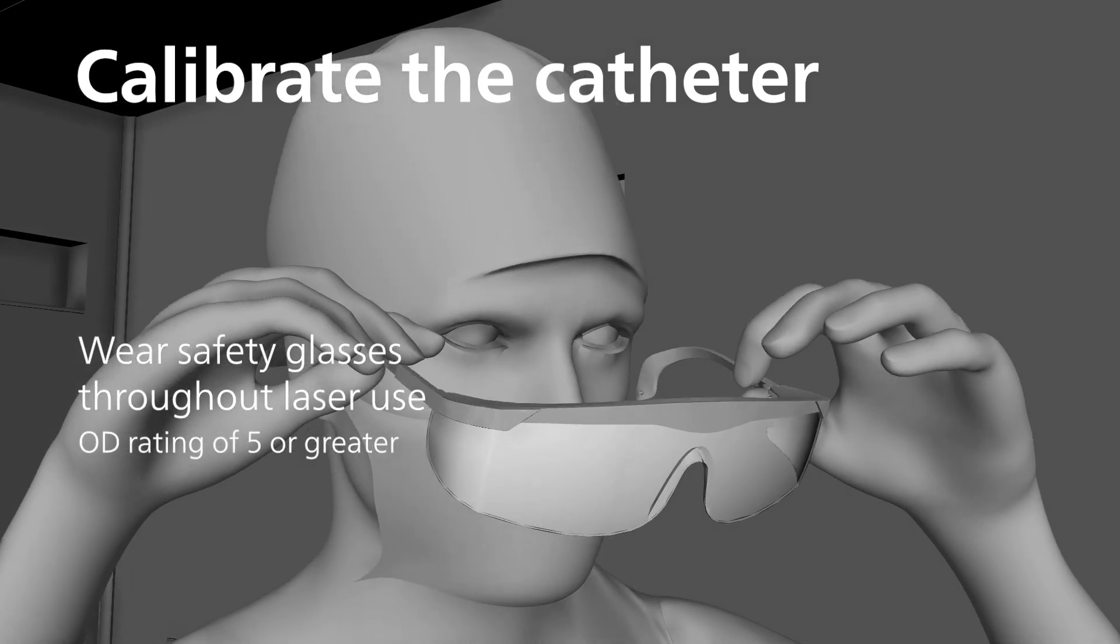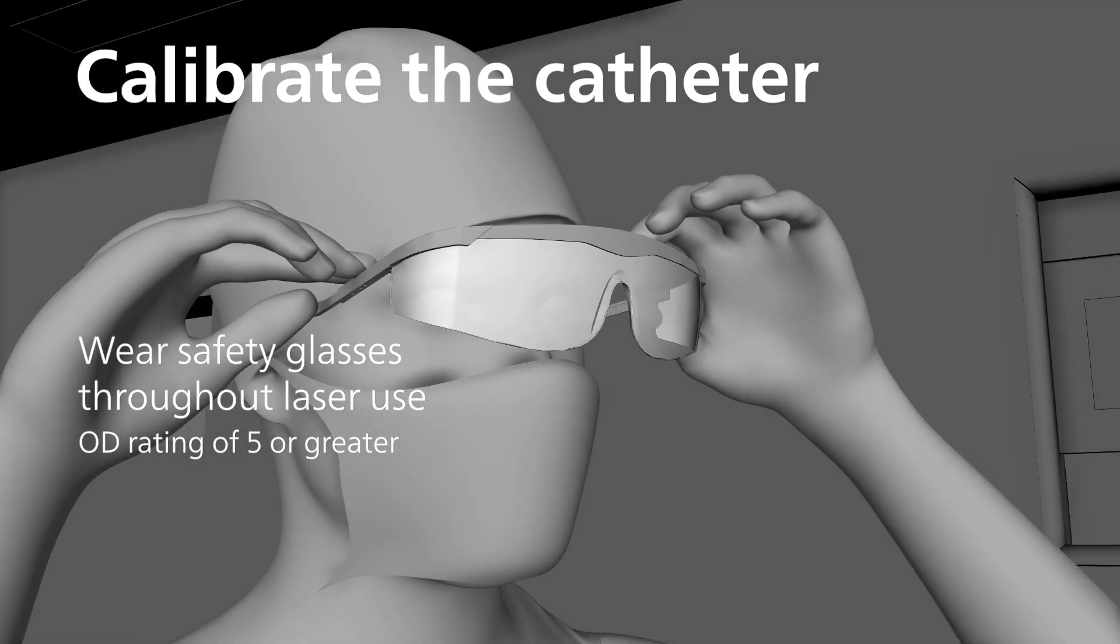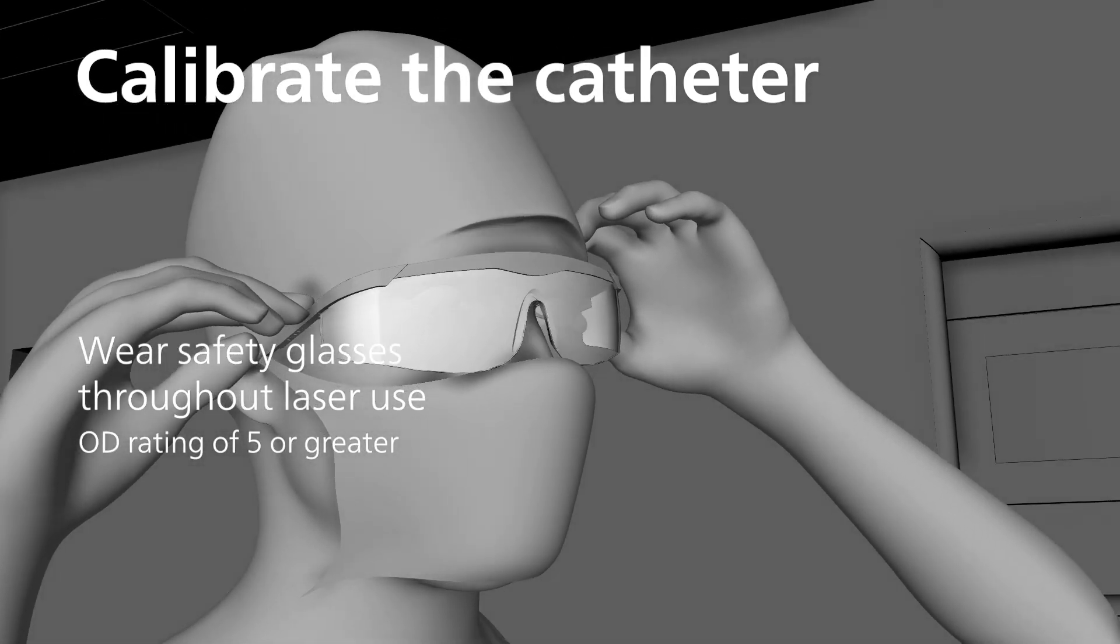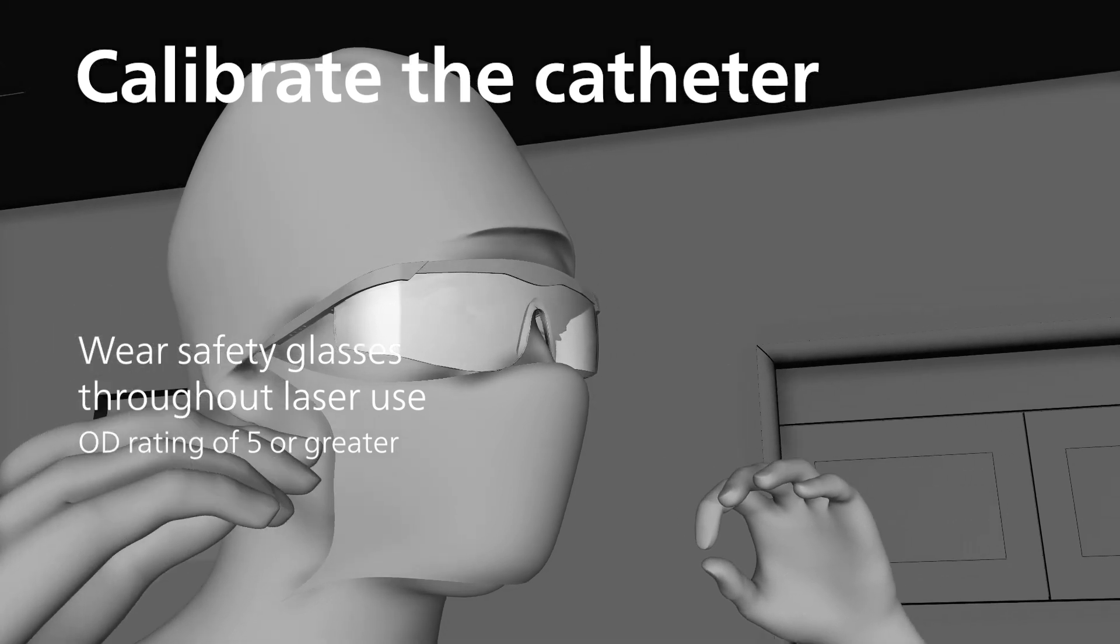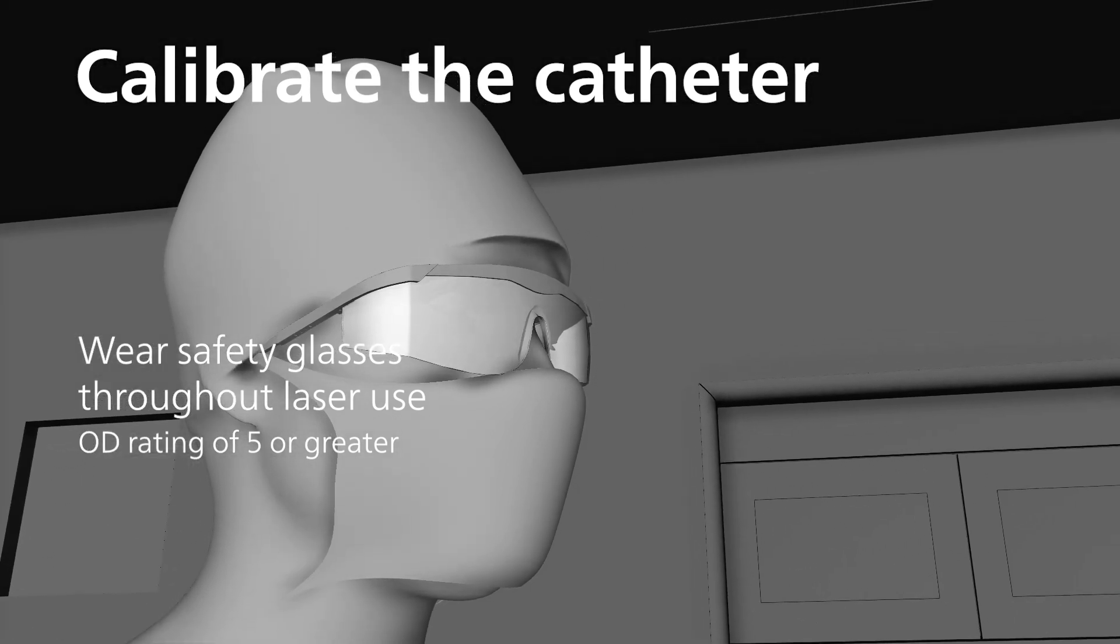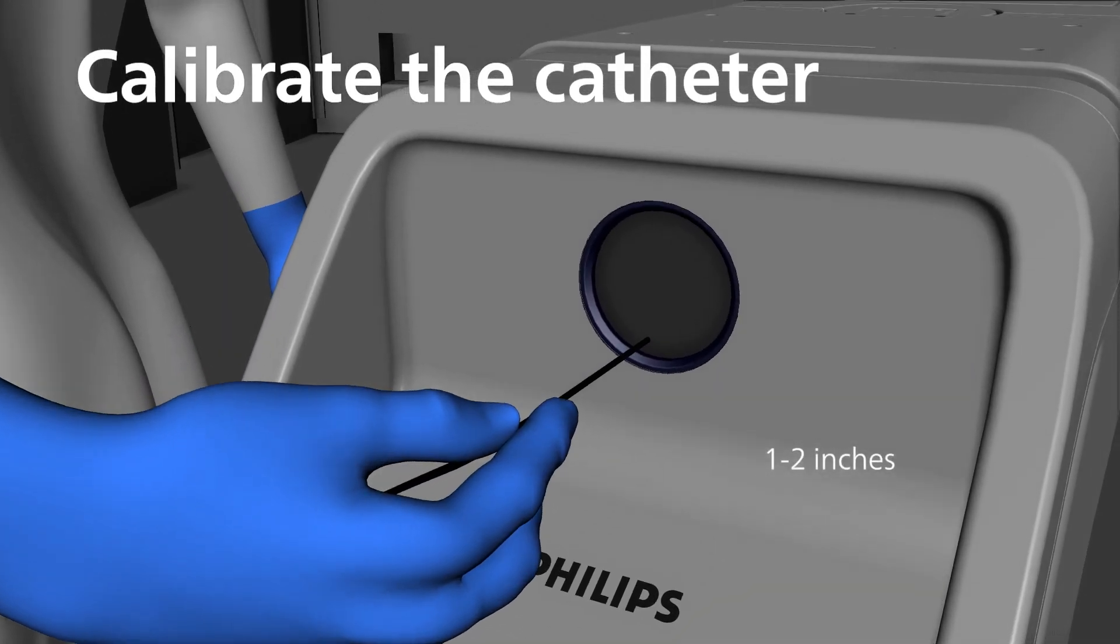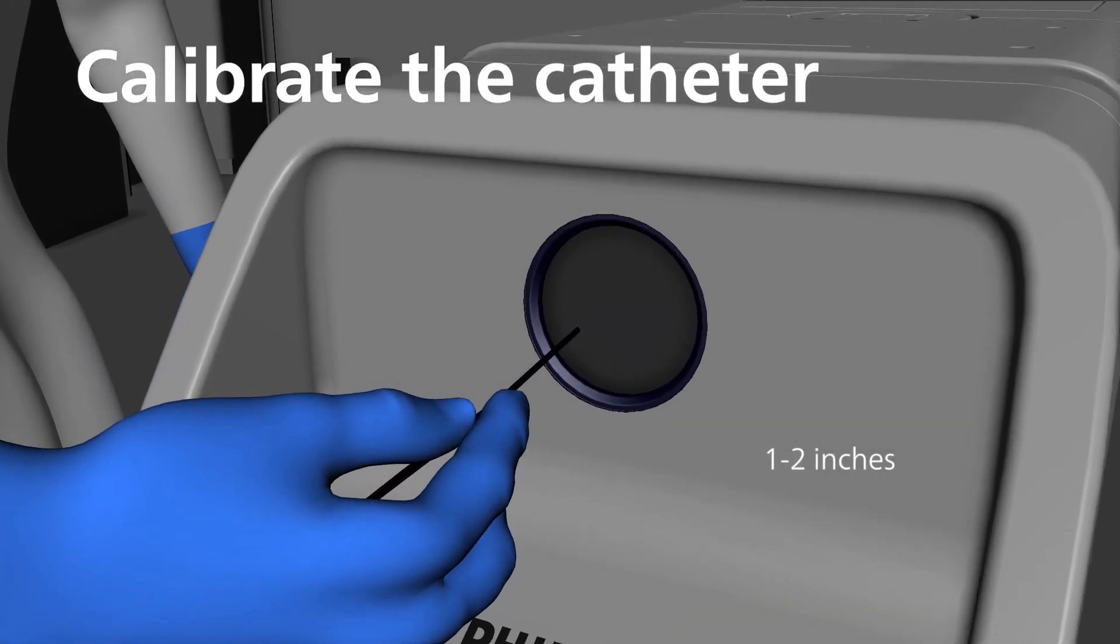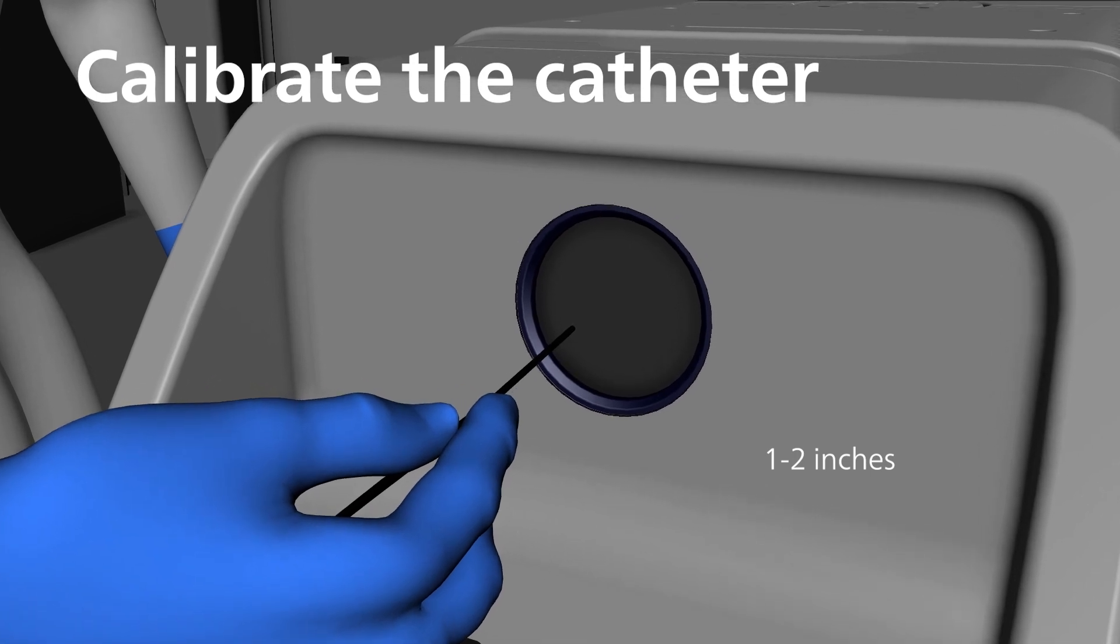Wear safety glasses with an OD rating of 5 or greater while laser is in use, including while calibrating the catheter. Point the distal tip of the fiber optic catheter directly at the center of the energy detector. Ensure the catheter placement is no less than 1 inch or 2.5 centimeters and no more than 2 inches or 5 centimeters away from the front surface. The end of the catheter will illuminate with a red light to aid in aiming the catheter.